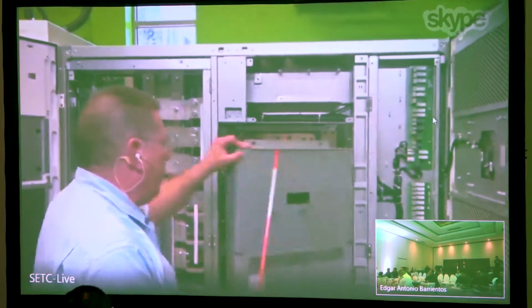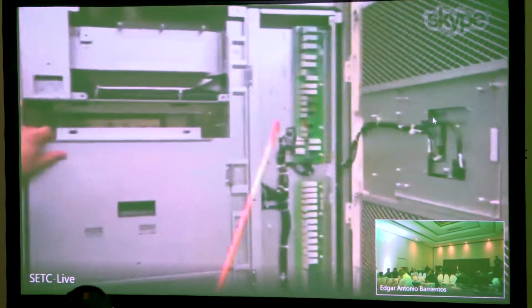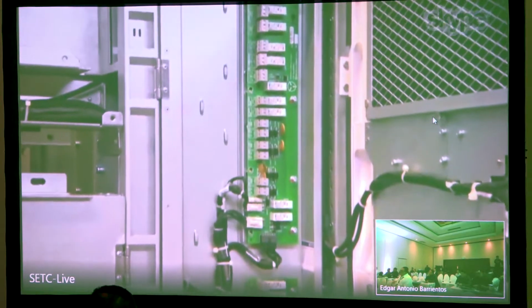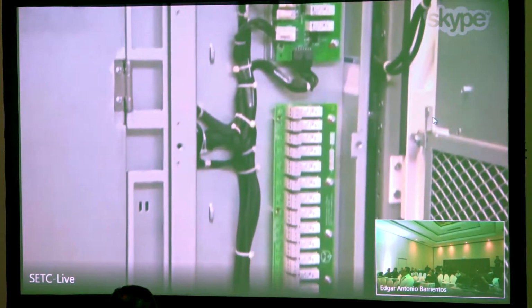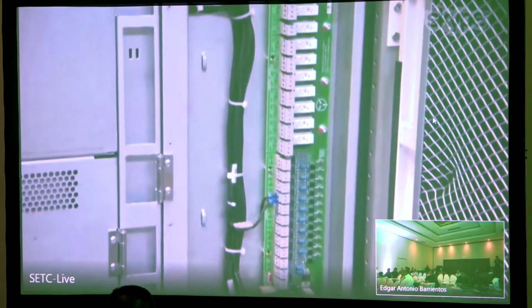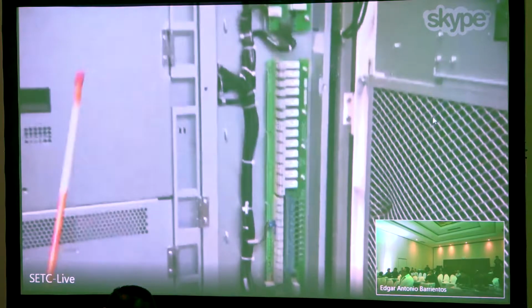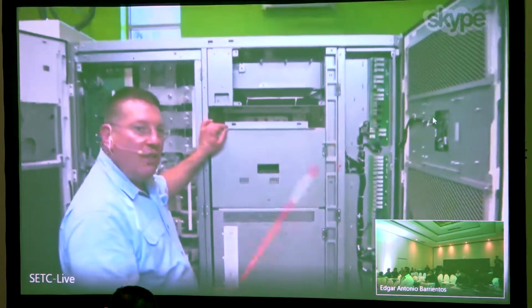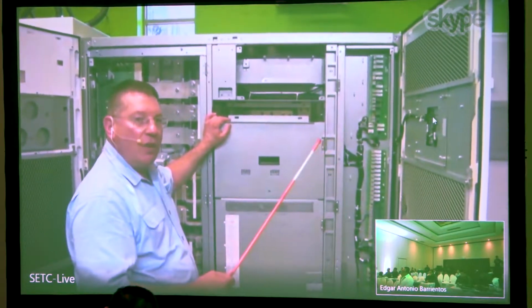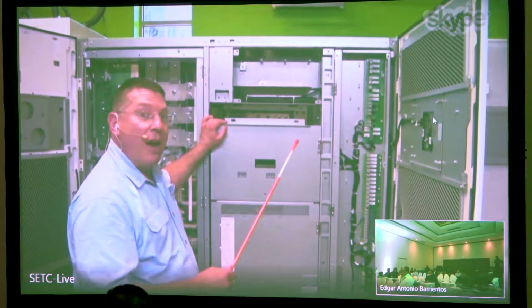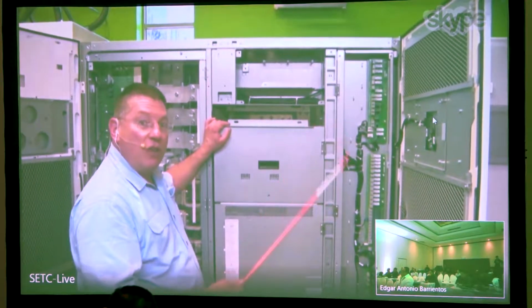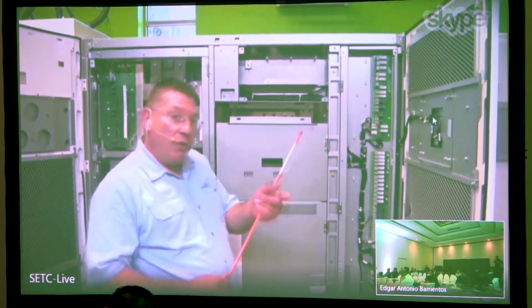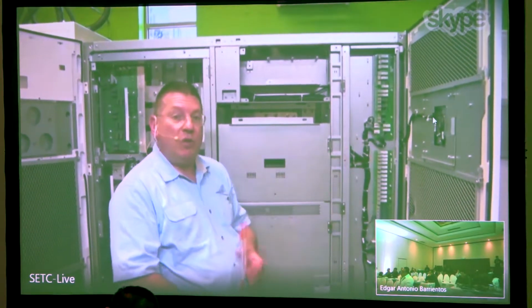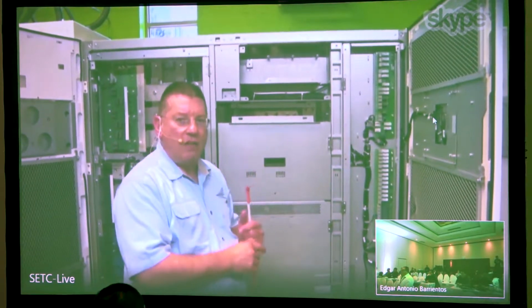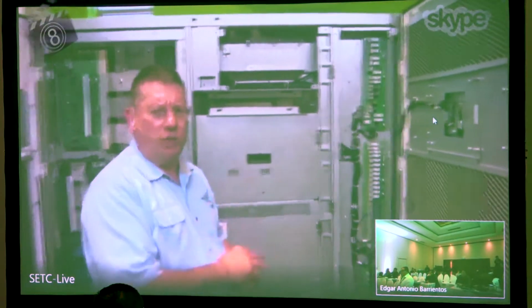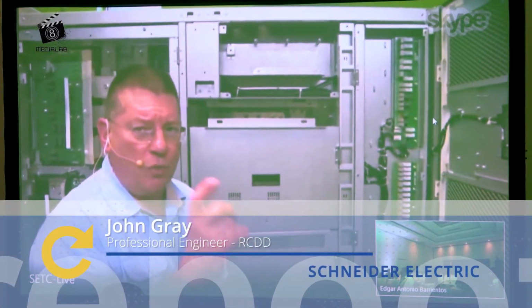Let's move a little bit over to the right. What I want to show you here is discrete input and output contacts. This is very, very adaptable, and we have some standard points. For example, on generator, that's a pretty important one to have. When we can tell the UPS we've got generator supply, we want to reduce our battery charging so we don't have to size our generator so big. When we're on generator we reduce our battery charging, and when we return to utility, we go back to full charging on the UPS. That's like a 0 to 40% of total capacity that we can do recharging at.